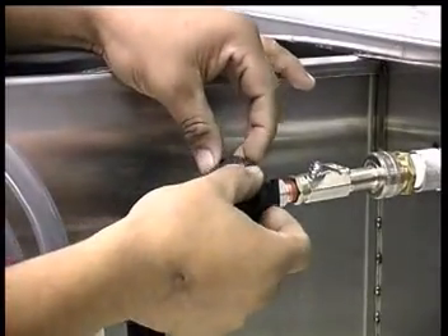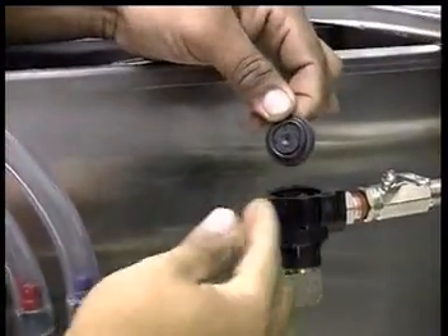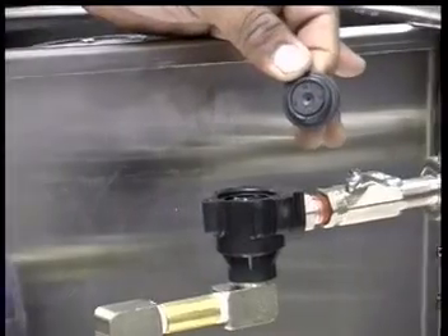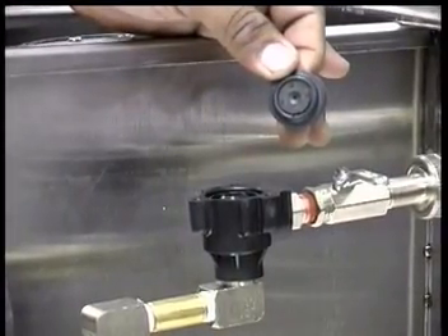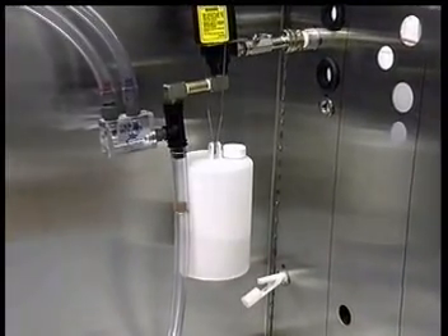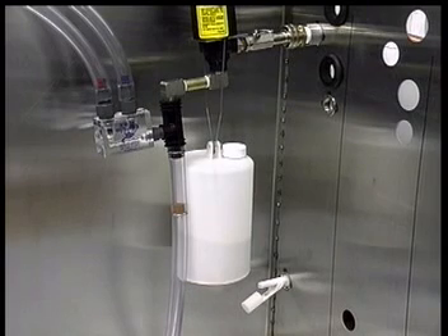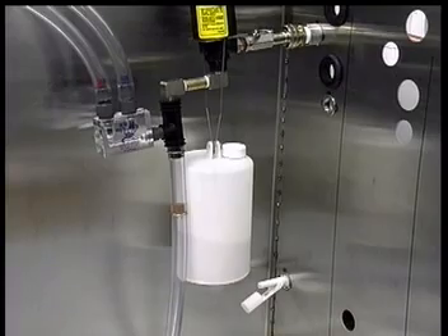This is a gasket material used to open and close the valve as controlled by the float. The diaphragm must be clean and free of debris. The on-off control of the Hydraminder is controlled by a float that raises and lowers with the liquid level. The float is weighted so it will pull down on the valve control when product drops below a set level. Make sure the float is not restricted as it travels.